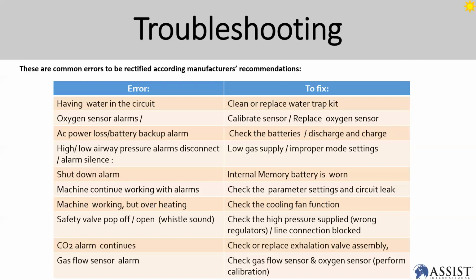CO2 alarm: that may be the exhalation valve assembly, or the sensor is not working properly. Then gas flow sensor alarm: check the flow sensor and oxygen sensor and try to perform calibration. That can solve the problem. If it does not solve the problem, check whether the sensor is working properly or not. This is very important when you do troubleshooting. Another best method: every ventilator brand has its own error codes. So it is better to look into the error code and refer back to the user manual, or if you have a service manual, refer back to the service manual. This is another fast way to do the checking. But these are the common errors you are going to find and how to fix them.